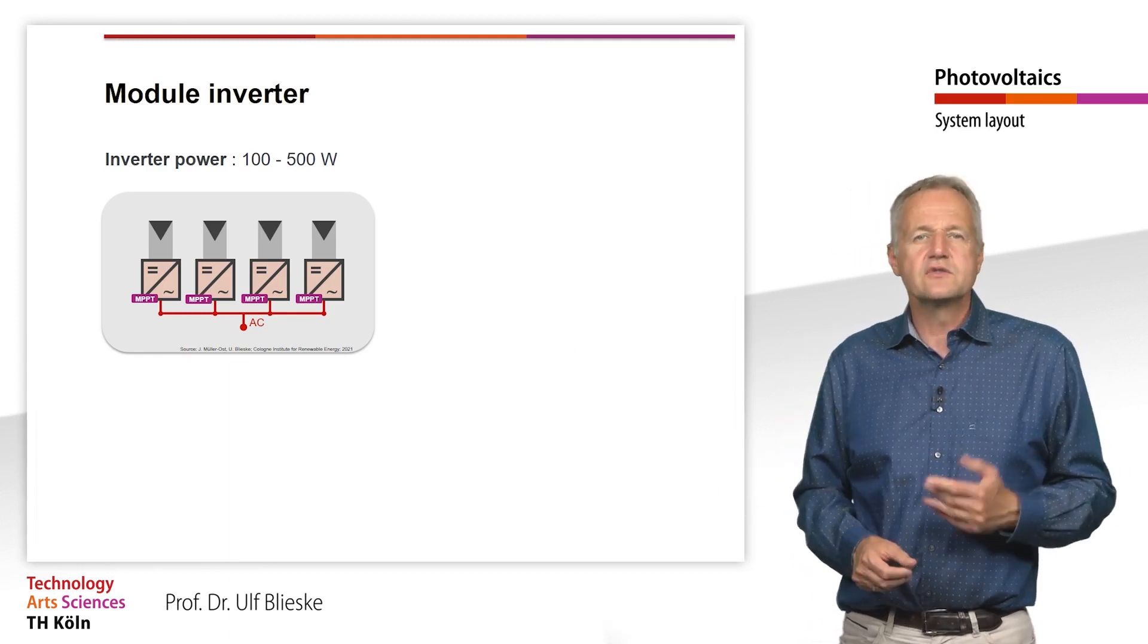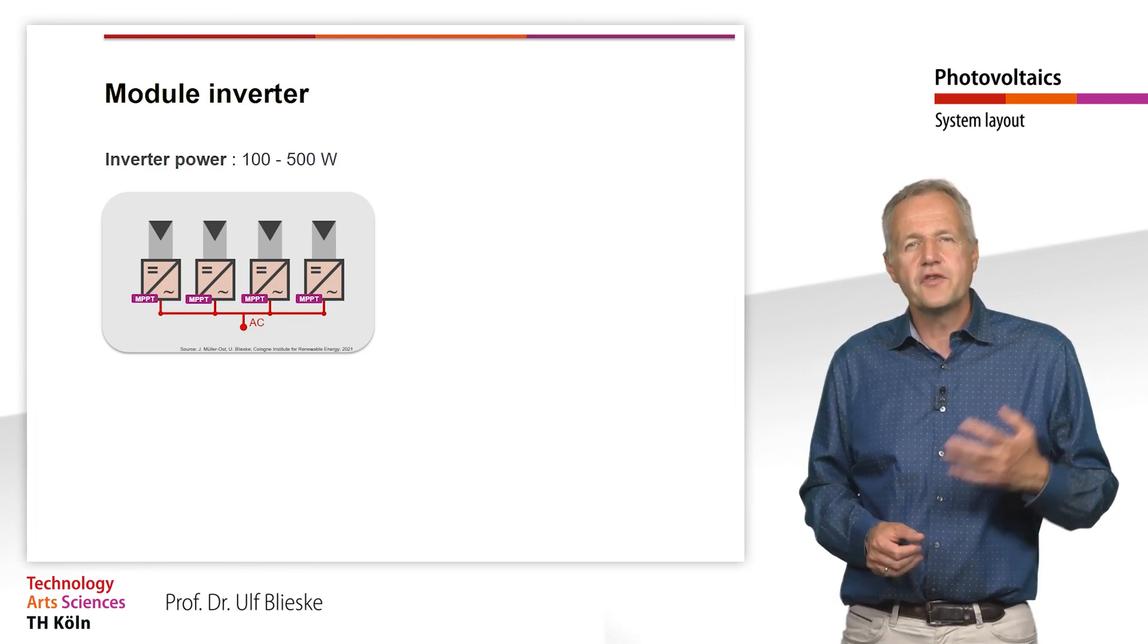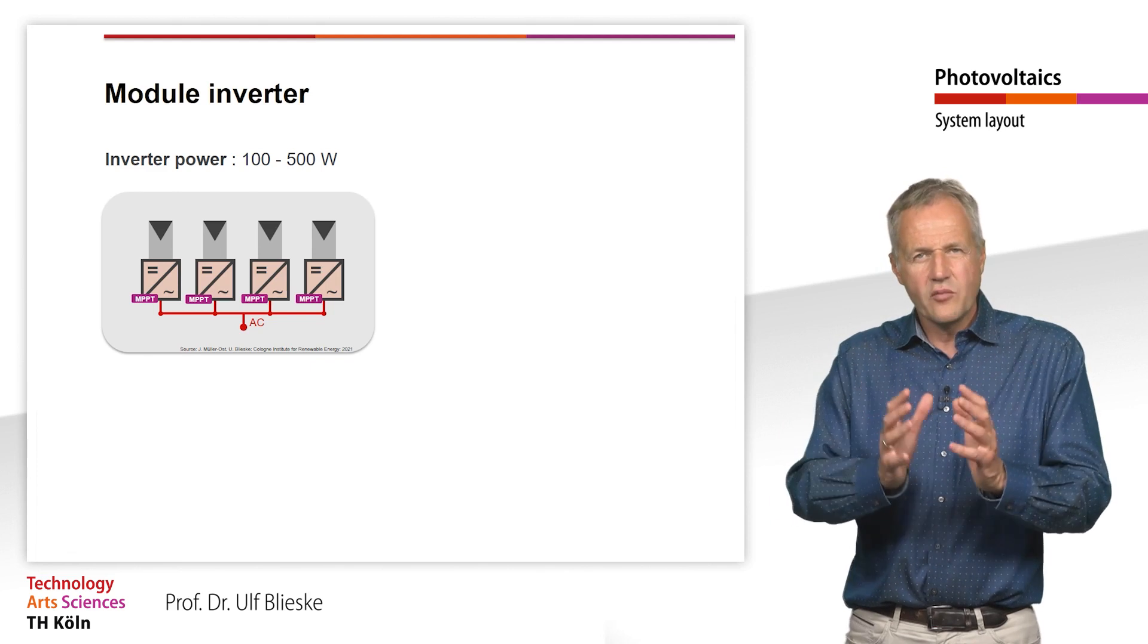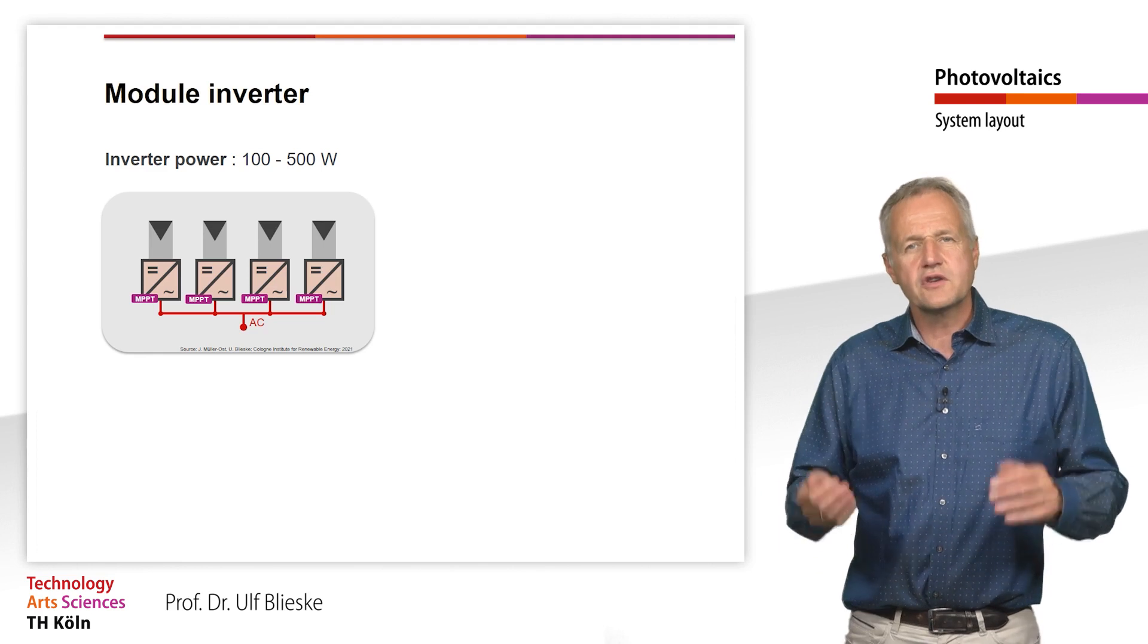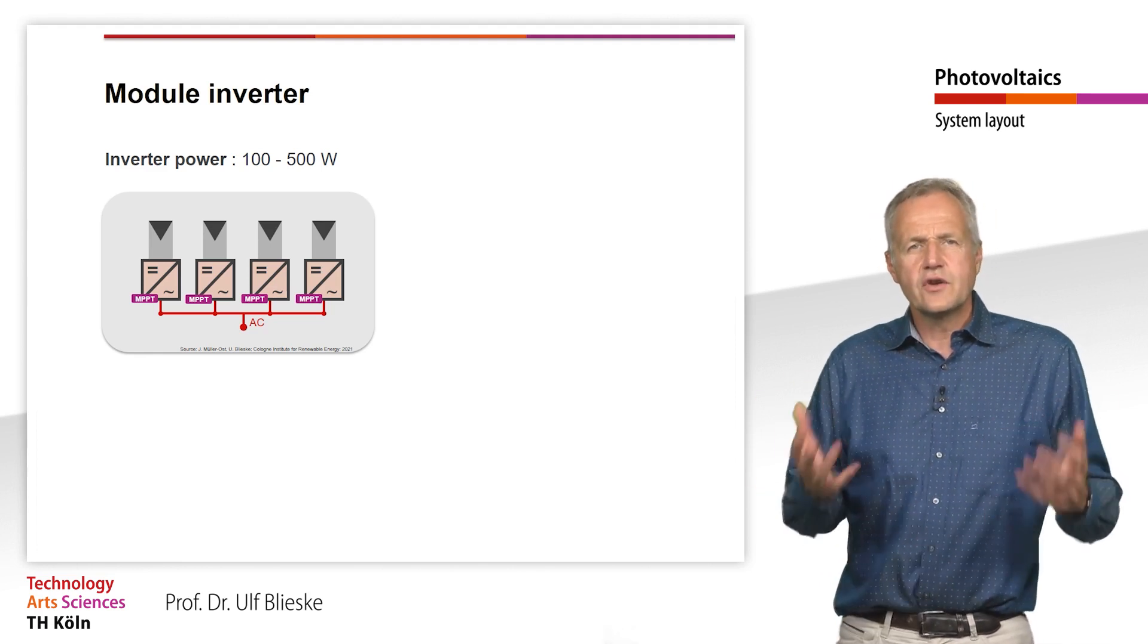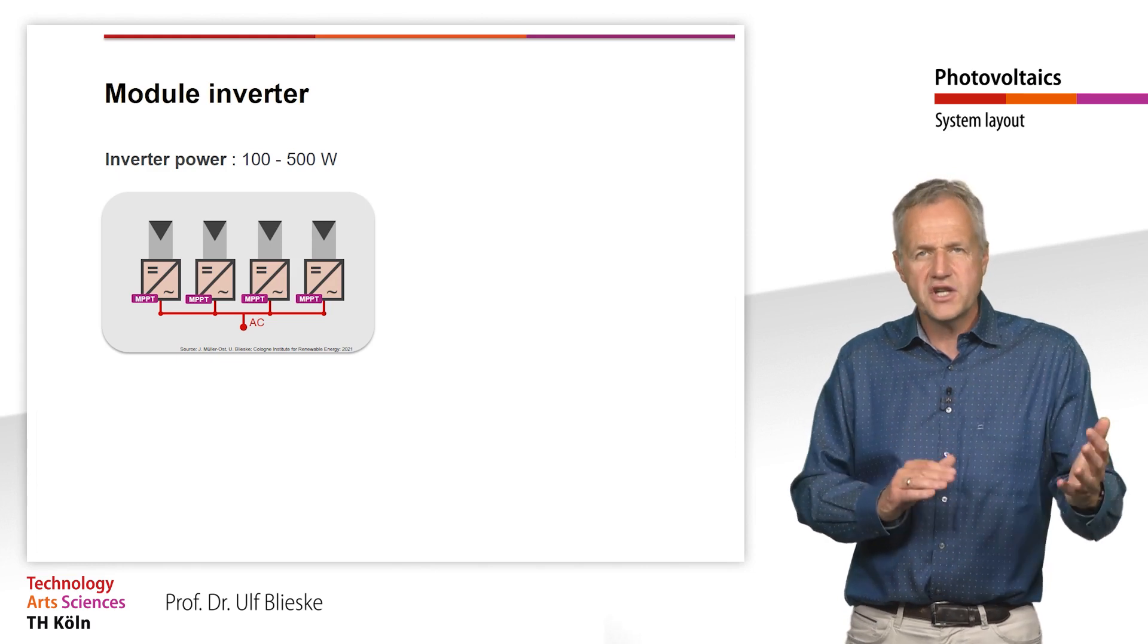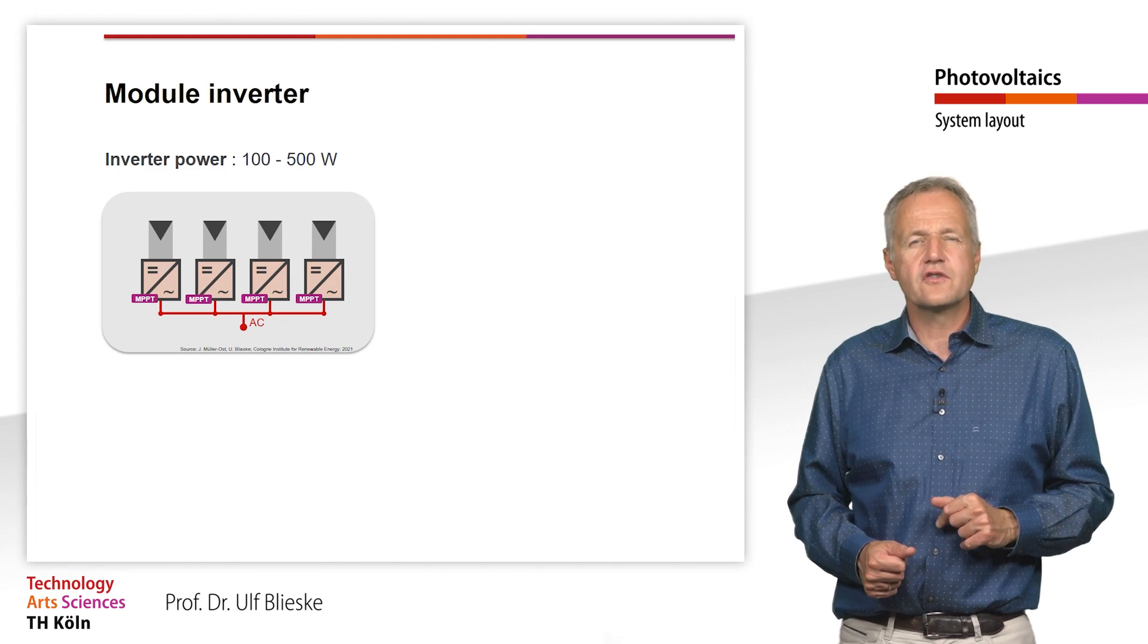Module inverters typically have power ratings of a few hundred watts and are connected to a single module at a time. They are relatively small devices, similar in size to a module's junction box. They are usually mounted on the back of the modules. Because each module has its own inverter, each module is always operated at its maximum power, regardless of the orientation or possible shading of the other modules. Thus, no mismatch losses occur in the system.